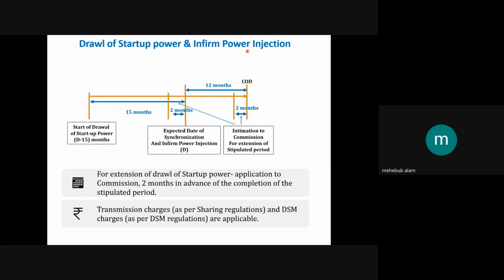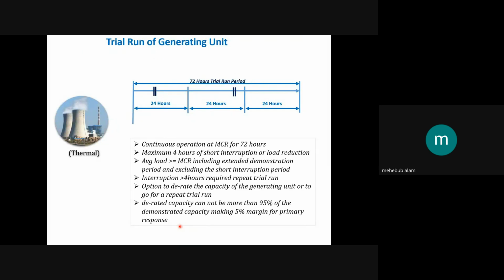And this infirm power will be governed by the DSM regulation, the deviation settlement mechanism regulation, because the power flow through the grid is very complex. Whenever any utilities or beneficiaries are pushing power into the grid, and the consumer is taking power, the utilities cannot push power without any limitation, because there is some regulation, and the pushing or transaction of power through the grid is guided by the deviation settlement mechanism. So that will be discussed later on.